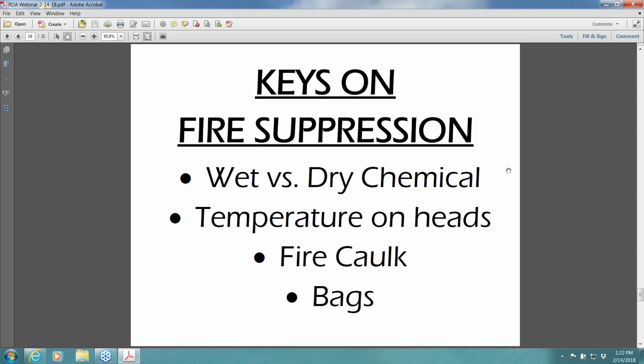One of the big conversations we get into is the temperature on the fire suppression heads. If you're dealing with a heated paint booth, an air makeup system on a paint booth is rated up to 200 degrees. Now, they usually have a high limit switch that stops them at 180. Doesn't mean it's going to be 180 in the booth, or if it is, it's not going to be there long, but you'll have a lot of fire suppression folks that will put in 160 to 180 degree heads. While in theory that should work, because it should never be that hot for an extended period of time inside the booth, it can get there.